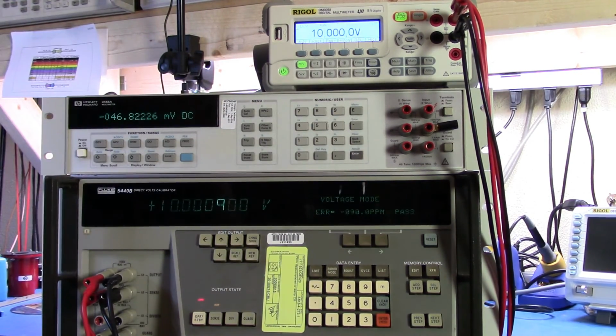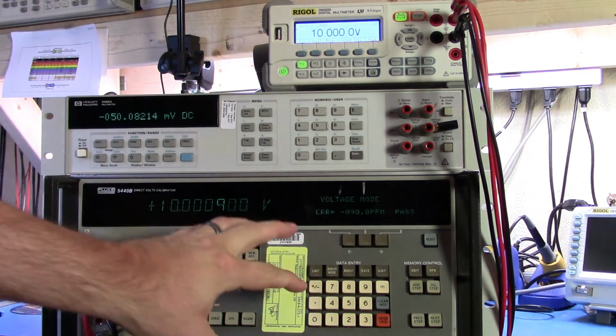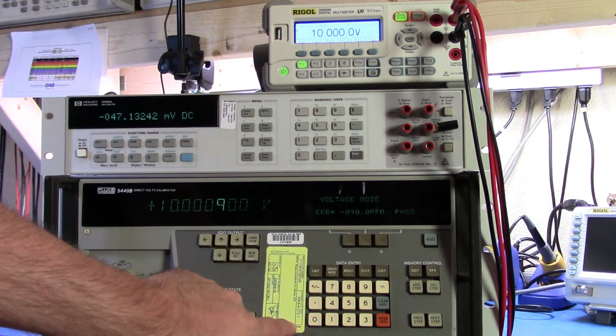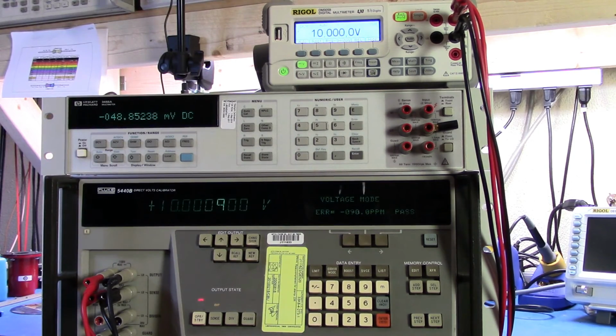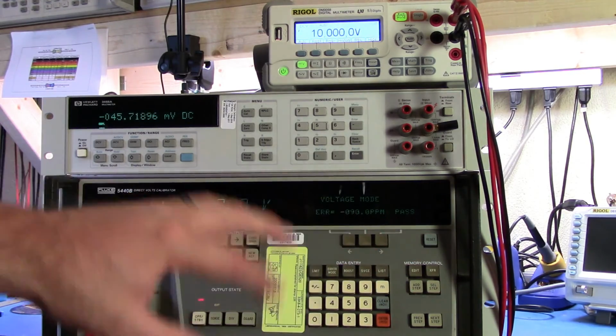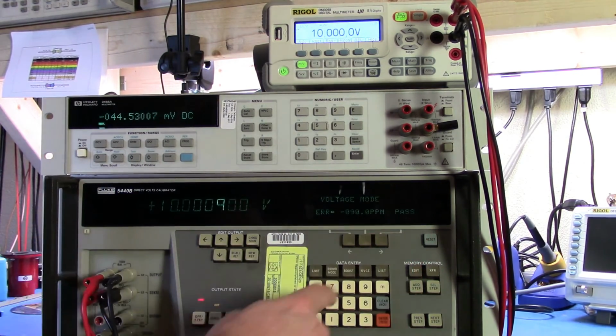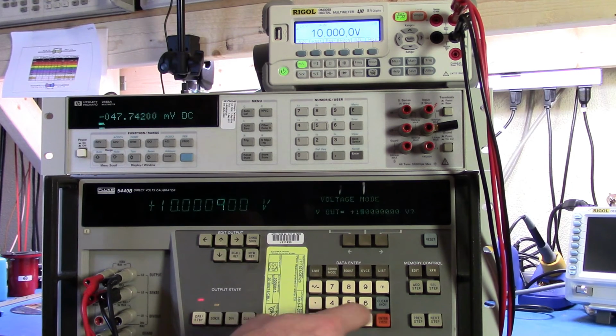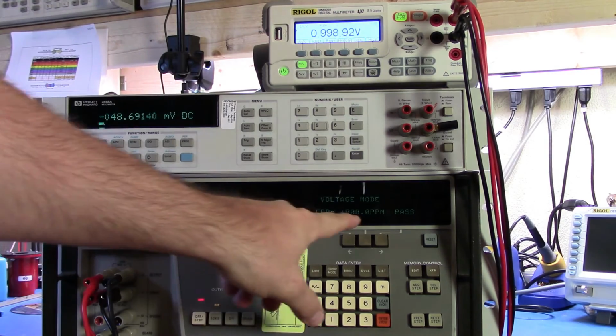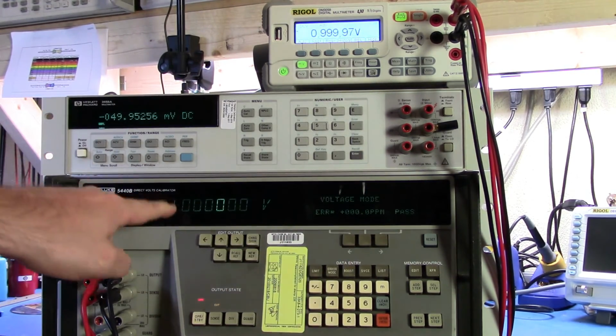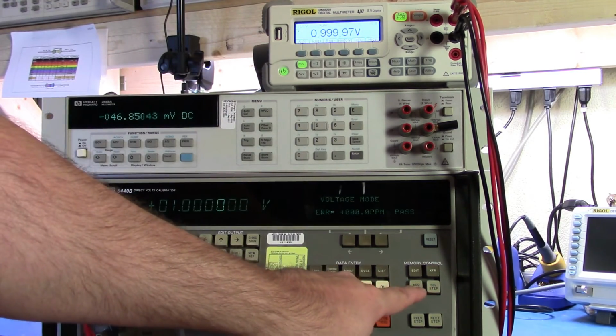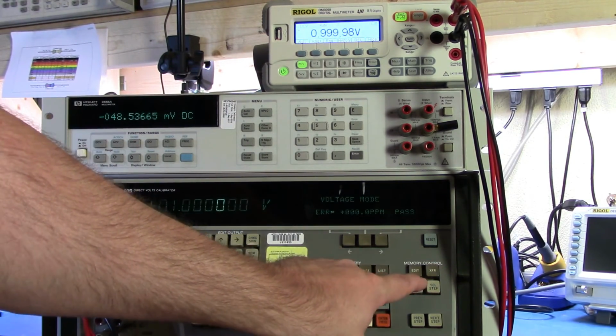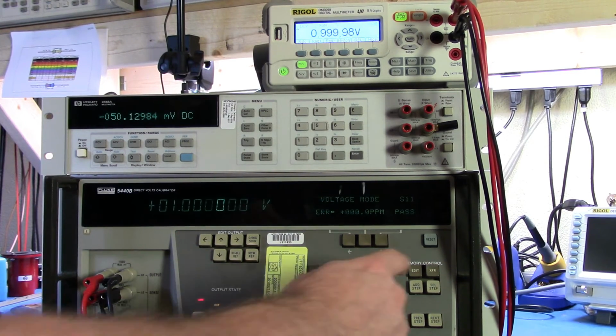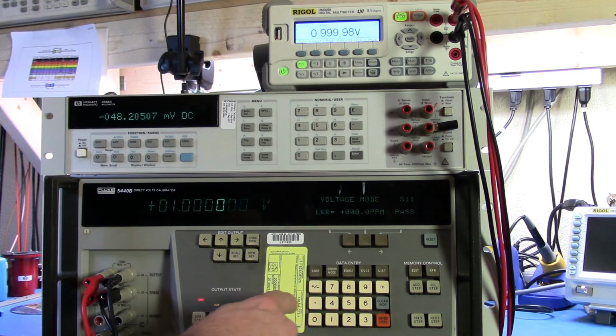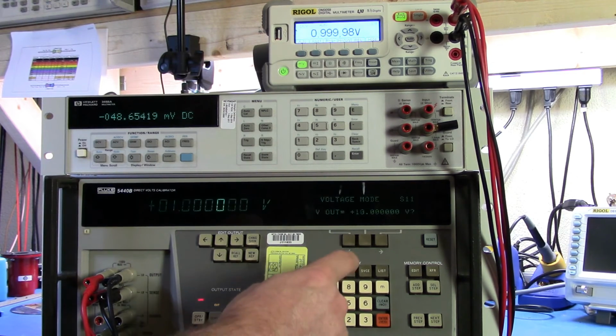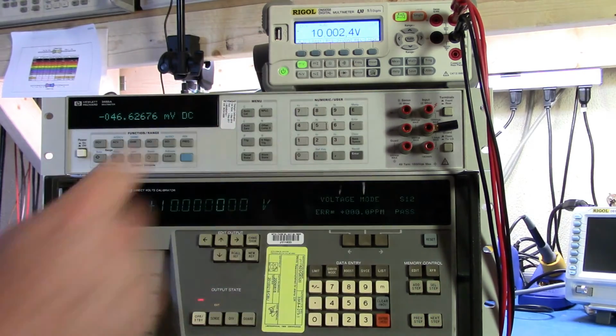Now when I set this up, one of the cool things with the B unit, and this is different from the B/AF, which is my other unit that's up with Fluke for getting manufacturer calibration, is I can create a little program here. The first thing that I might want to do is set 1 volt, and let's just assume that my error values all stay the same. So with 1 volt, that's what I'm going to measure. I can just say, let's add this as a step. Then let's maybe make 10 volts. I can enter that, set the unit up, and add that as a step.